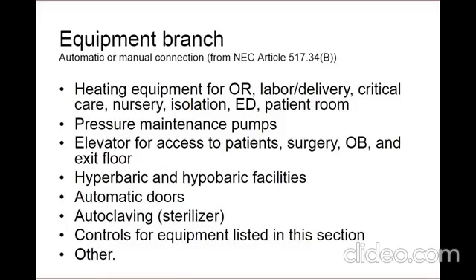And then Part B of the equipment branch is what is permitted to be manually connected. Again, nothing precludes you from connecting this stuff automatically. The code just allows it to be a manual connection as an acceptable means. This includes heating equipment serving operating rooms, labor and delivery rooms, critical care rooms, nurseries, which include NICUs, isolation rooms, emergency departments, and patient rooms. Note there are also some exceptions here depending on the climate you're in and what that ASHRAE design temperature is.